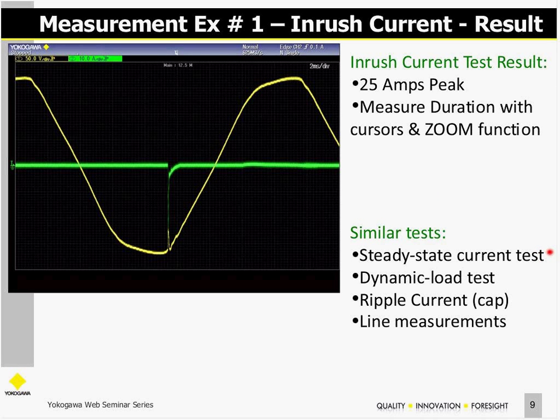I can also move the current probe over to the capacitor. That might require some modifications to the power supply, but I could measure the in-rush current or the ripple current into the input capacitor as well. You might use the same connections for a steady-state current test or a dynamic load test, to watch the current at the input of your switch mode supply during a dynamic load change, again looking at ripple current and other line measurements, which we'll discuss later.